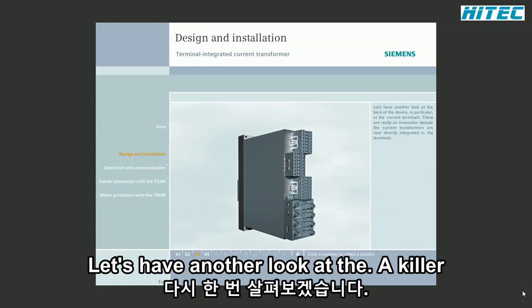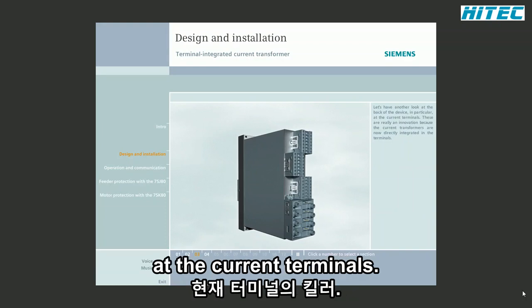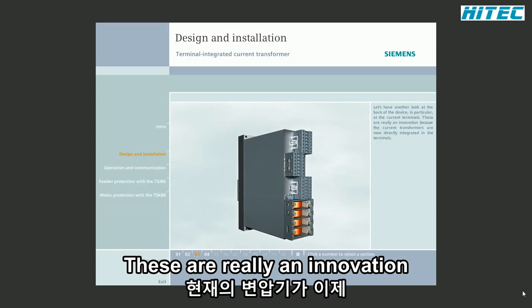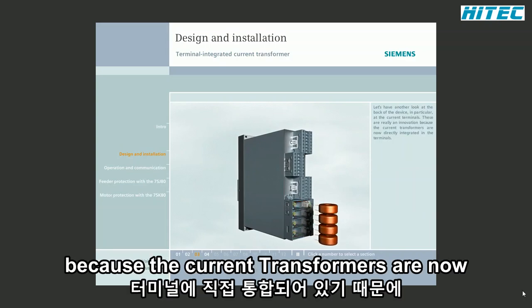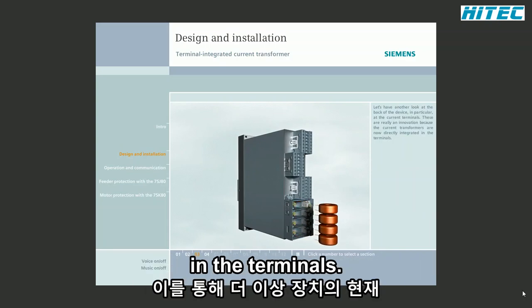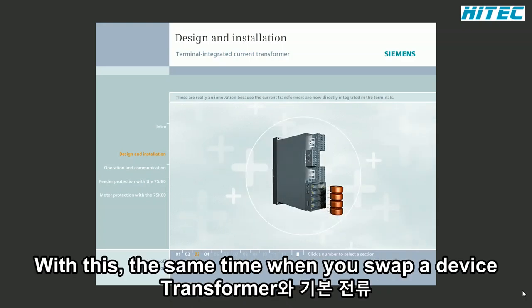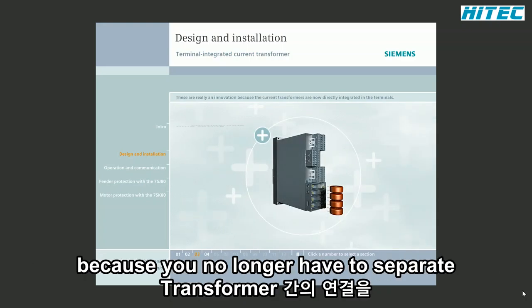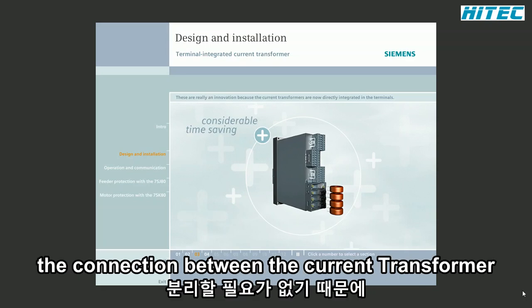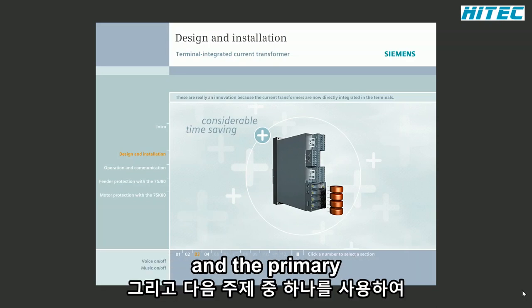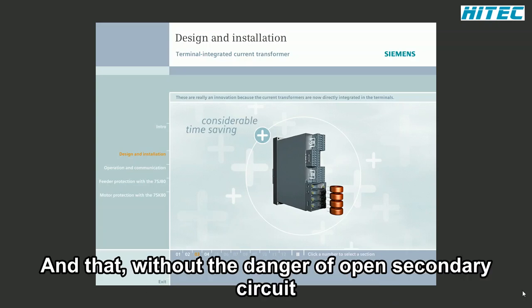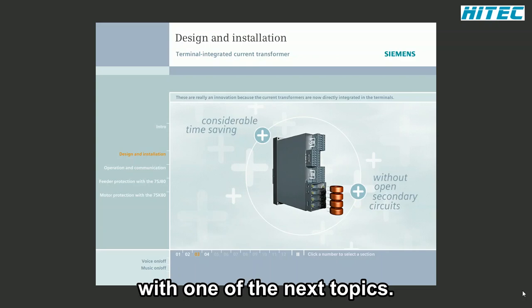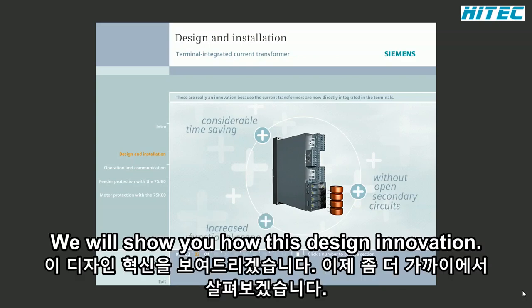Let's have another look at the back of the device, in particular at the current terminals. These are really an innovation because the current transformers are now directly integrated in the terminals. With this, you save time when you swap a device because you no longer have to separate the connection between the current transformer of the device and the primary current transformer, and that without the danger of open secondary circuits. With one of the next topics, we will show you how this design innovation also has a positive effect on the functional scope.